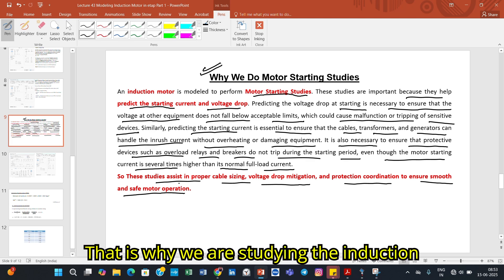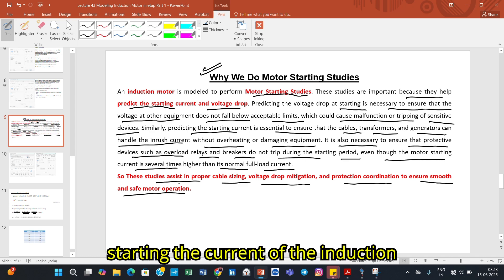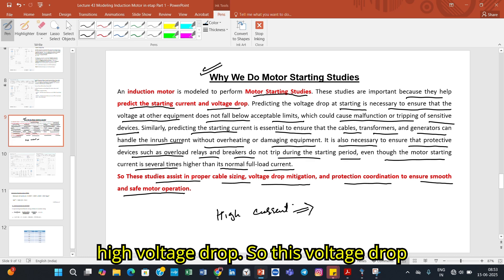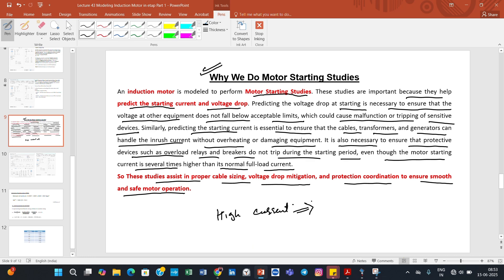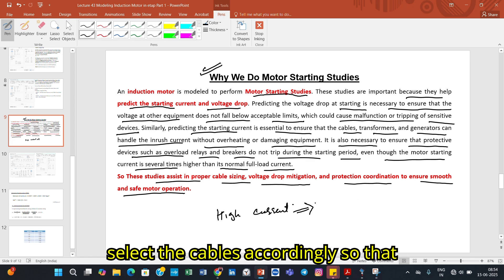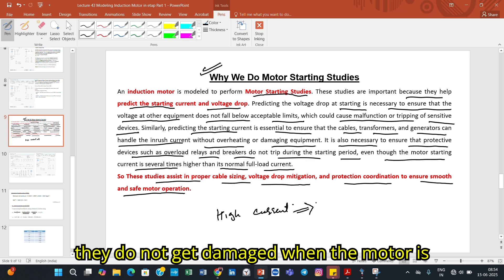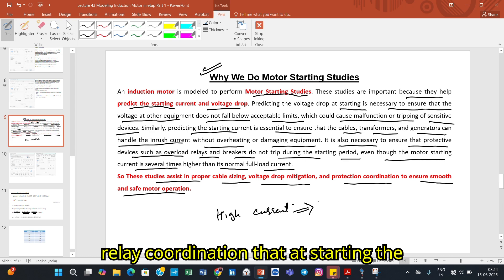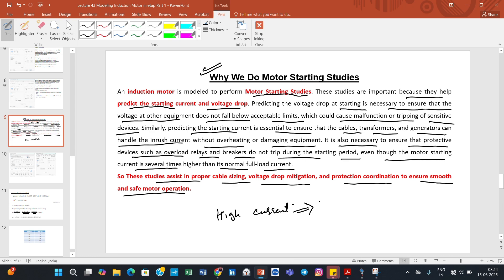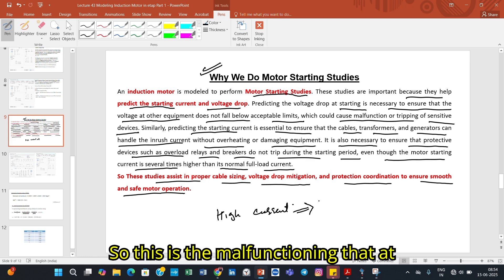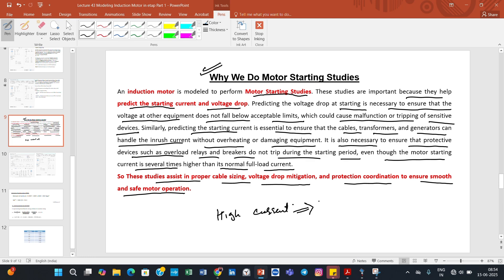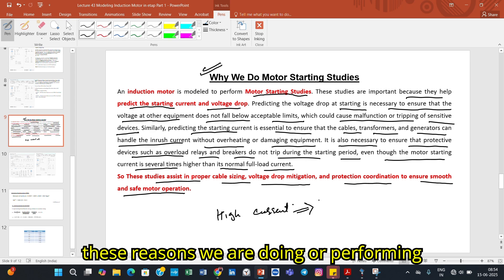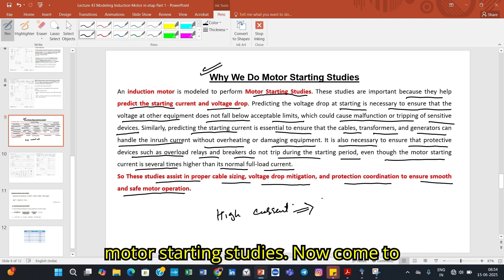That is why we study induction motor starting studies — because at starting, the current is very high, which causes a high voltage drop. This voltage drop should be within acceptable limits. When the current is high, we select cables accordingly so they do not get damaged. Another consideration is relay coordination: at starting, the current is very high by nature, and we do not want the relay to trip at that time. These are the reasons we perform motor starting studies.